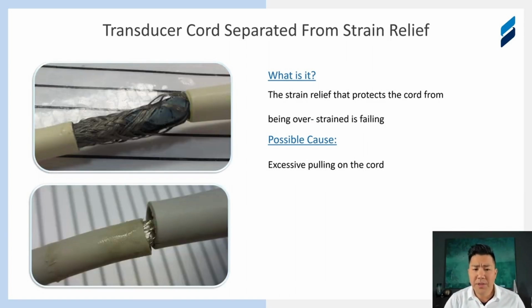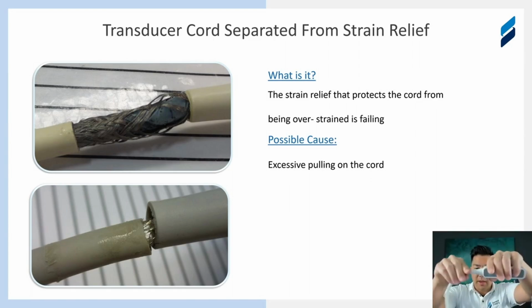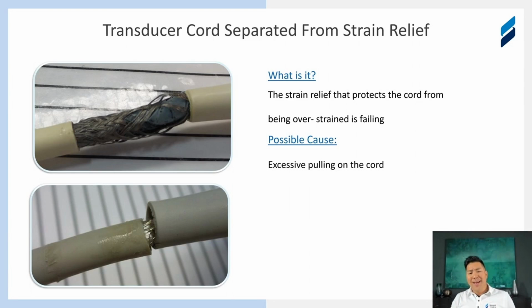Another common failure for transducers is the cord separating from the strain relief. So we're talking about the strain relief of the transducer that's attached to the cord here. This is compromised and it's now separated from the cord, exposing the internal electronics. Same thing on the other side, at the connector, where we have the strain relief here and the cord, and it could be separated here too. Now, how does this happen? This happens when the cords are really pulled on pretty hard.